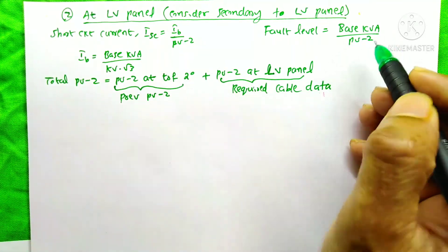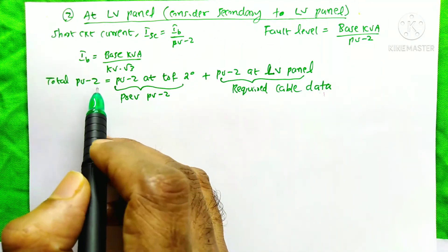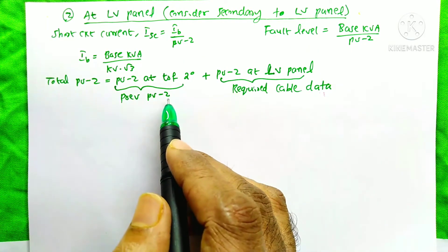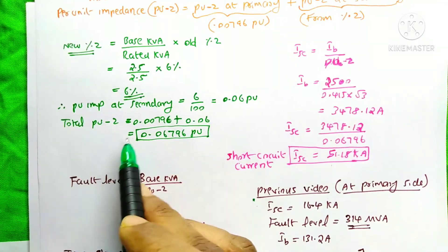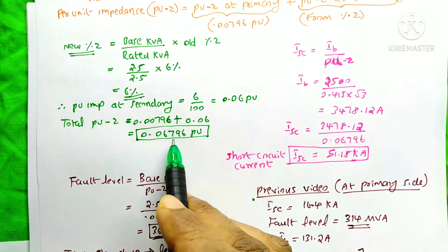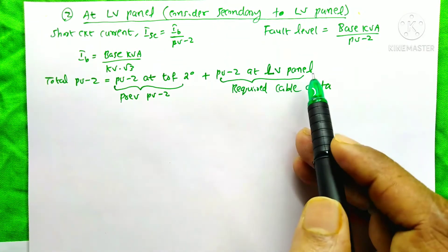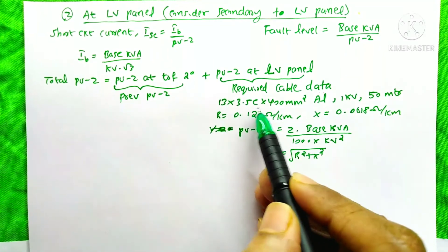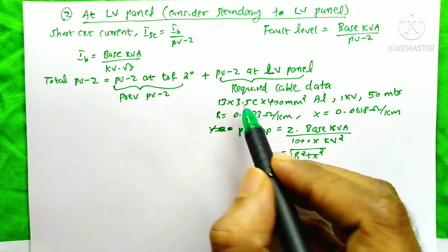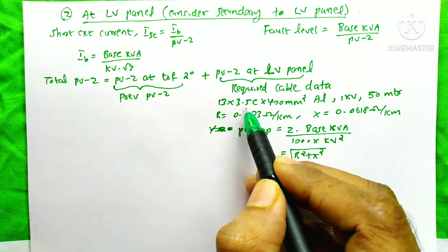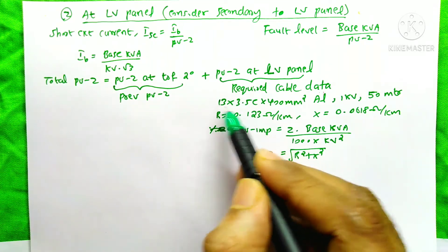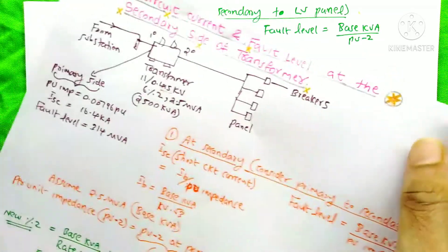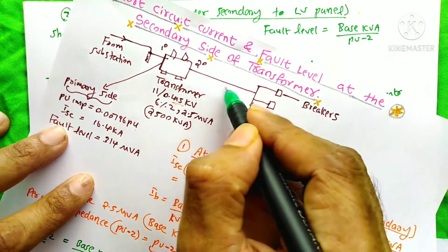The total per unit impedance equals the per unit impedance at the transformer secondary — which is 0.06796 from our previous calculation — plus the per unit impedance at the LV panel. For that, we need the cable data. The cable is 13 runs, 3.5 core, 400 mm² aluminum conductor, rated 1 kV, and 50 meters long from the transformer secondary to the panel. The resistance is 0.123 Ohm per kilometer and the reactance is 0.0618 Ohm per kilometer.